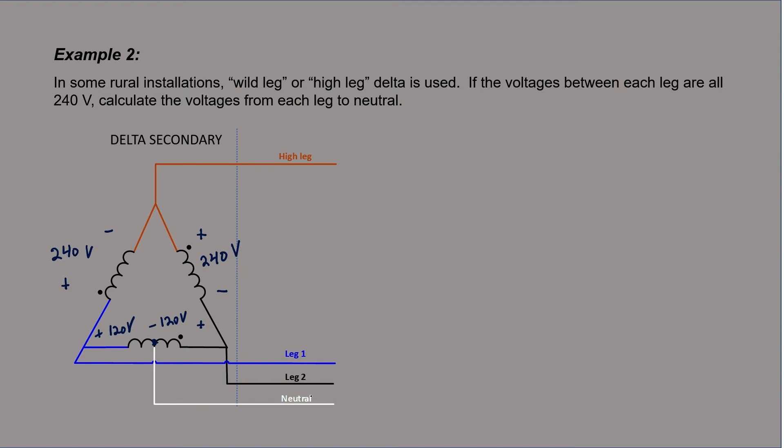In this diagram, the center tap becomes the neutral wire, and I've colored it white to match the typical color code used in North America. One of our phases is colored black, another phase is colored blue, and then our high leg, or the wild leg, is colored orange, and that's by convention.